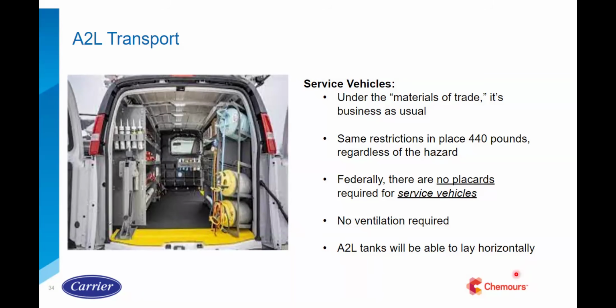So Chemours and the refrigerant manufacturers went to the U.S. Department of Transportation and talked to them about whether this stuff counts as "materials of the trade." I'm putting it in quotes because I don't know exactly what that means, but somehow if you have a service van and you're transporting materials for your trade of work, HVAC, to be installed at a project site, that makes you legally different than a delivery truck driving down the road. Even though you may both have the exact same quantity of chemical in your vehicle, somehow you're different than they are. And as long as your total chemicals do not exceed 440 pounds, you don't have to do any of the placarding or the ventilation or any of that stuff.